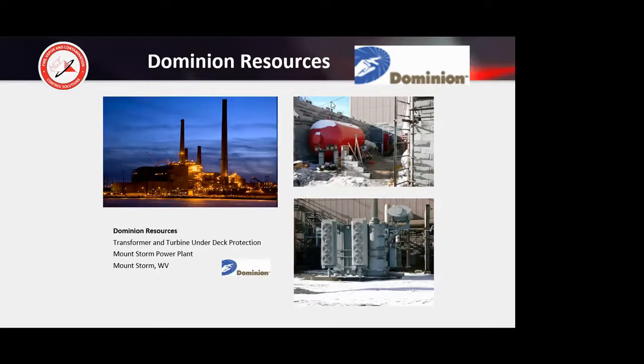This is in Mount Storm Power Plant in West Virginia. This one had 2 3,000-gallon bladder tanks. We provided the snow on the top at no extra charge. This 3,000-gallon bladder tank is protecting Unit 1 and Unit 2 under turbine lube oil systems, and it's protecting 5 transformers. On the other side of the building, they are building another firehouse. It also has a 3,000-gallon bladder tank, and it is protecting Unit 3 under turbine, as well as 10 transformers. So all in all, 3 under turbine lube oil fire protection, and 15 step-up transformers. Call these step-up station transformers, sometimes SST for short.